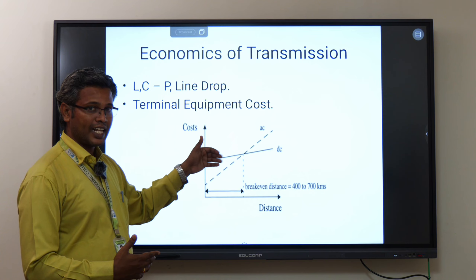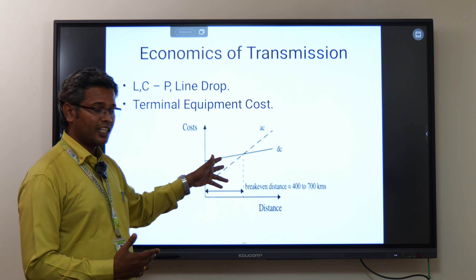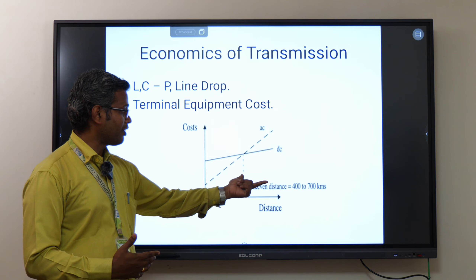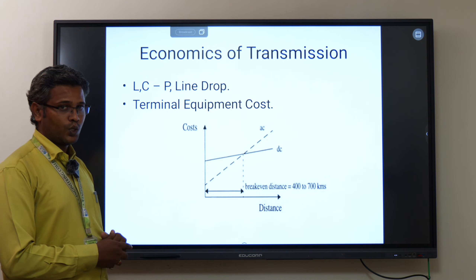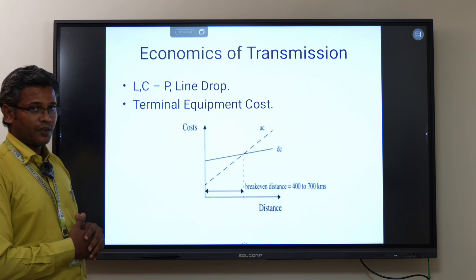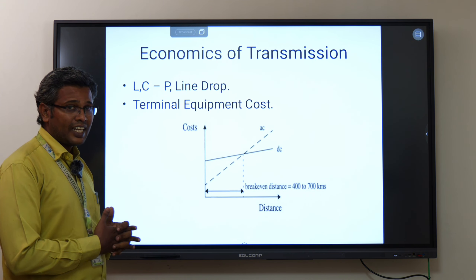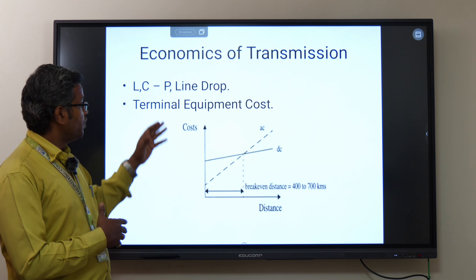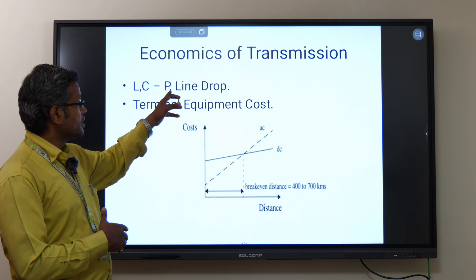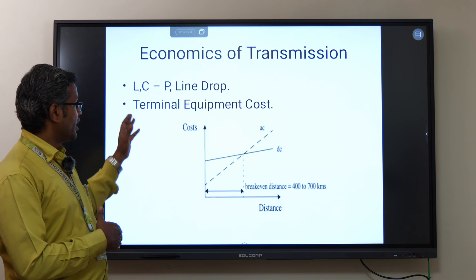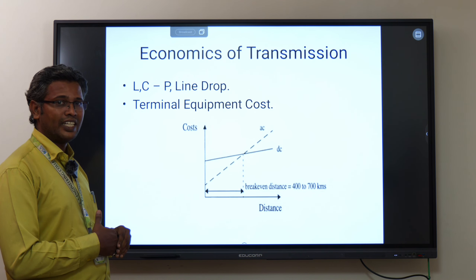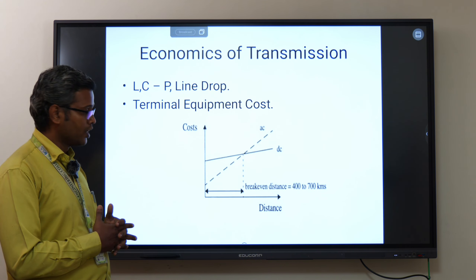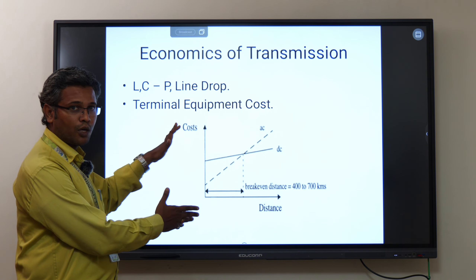Above the break-even distance, if you want to transmit electrical power, we prefer DC. The break-even distance varies from 400 to 700 kilometers depending on several factors. For DC transmission, we do not consider inductance and capacitance — only resistance plays a major role — and the power transfer capability is more. Also, line drops are less in DC transmission, and terminal equipment cost will be less for long-distance DC compared to AC transmission.